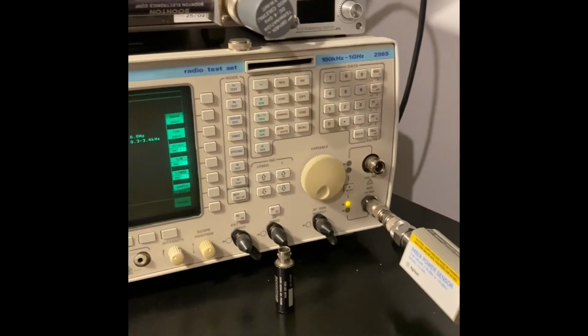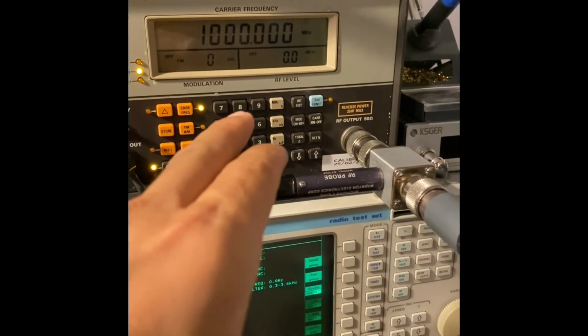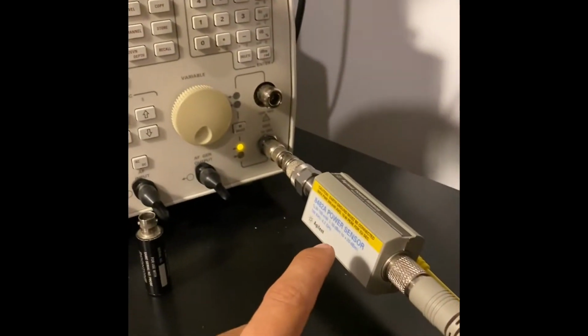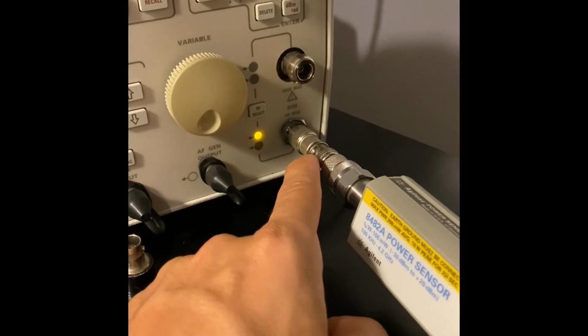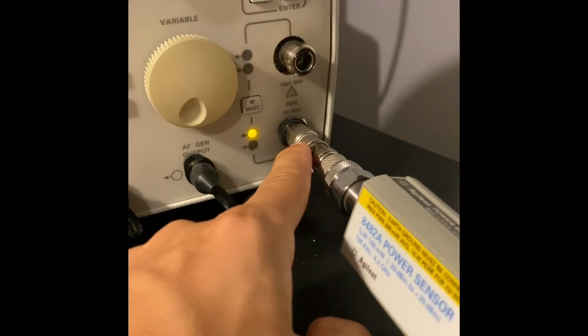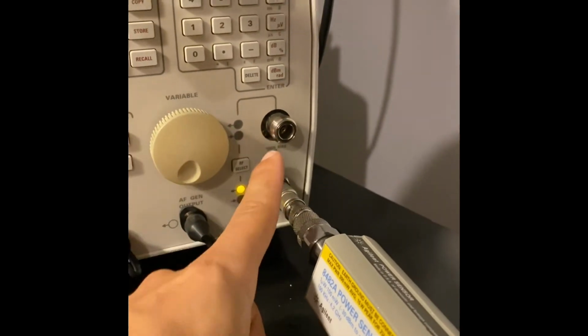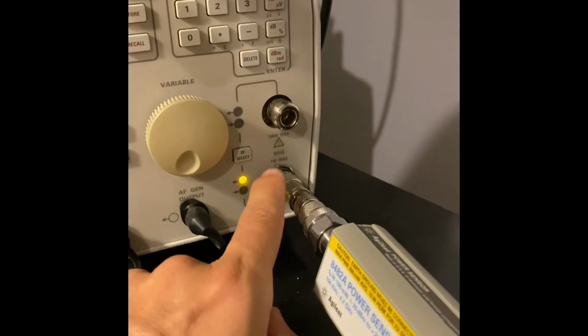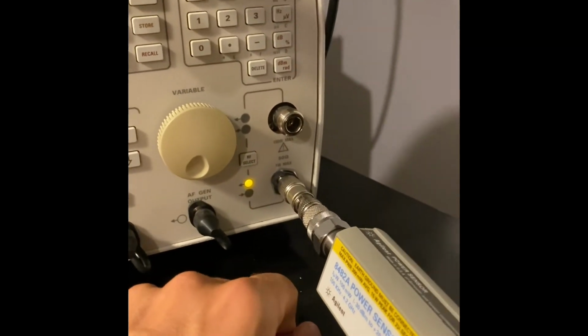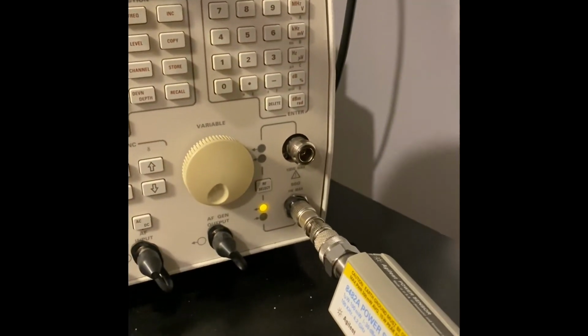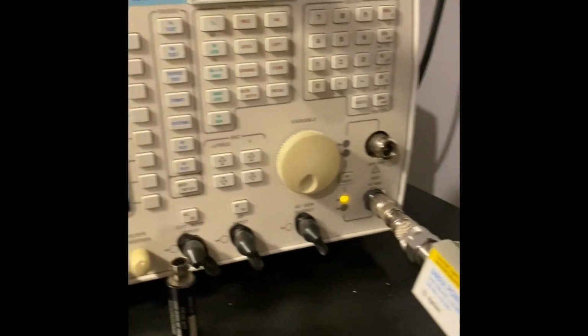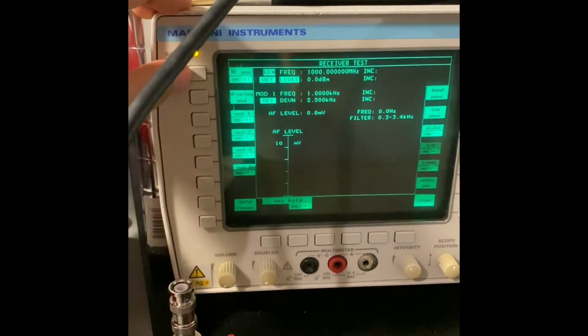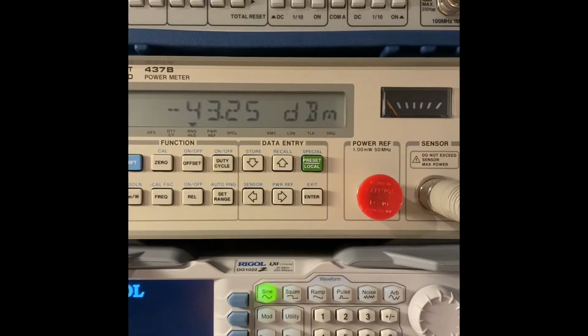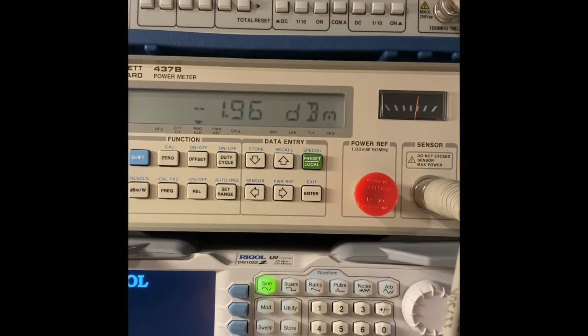Okay, now the BOONTON is hooked up to the 2022, and the power sensor is connected to the TNC port, which is the bottom one. We'll check also on the N port. The specifications are not exactly the same from the manual, from Marconi, but we check both. So 1 gig, 0 dBm. It was reading -2 on the BOONTON. Let's switch the gen on. Let's see what the HP thinks about it.